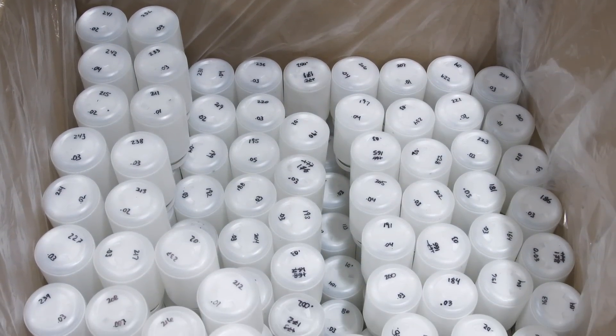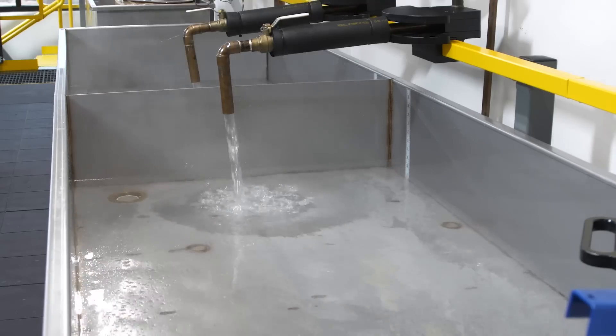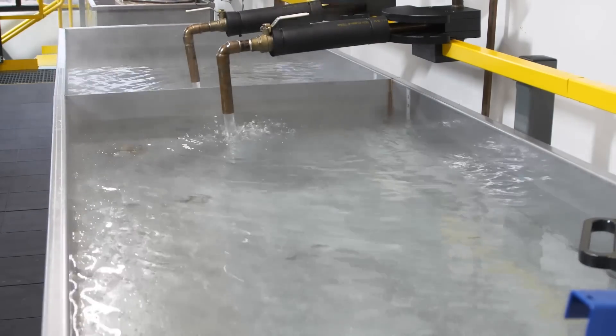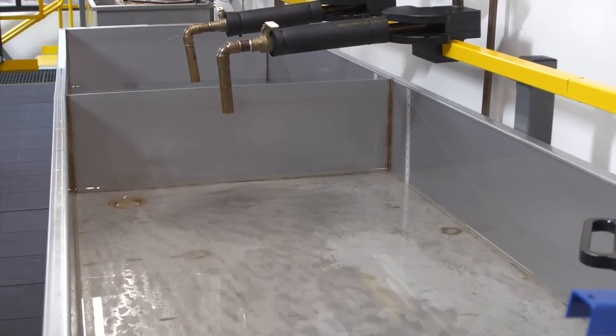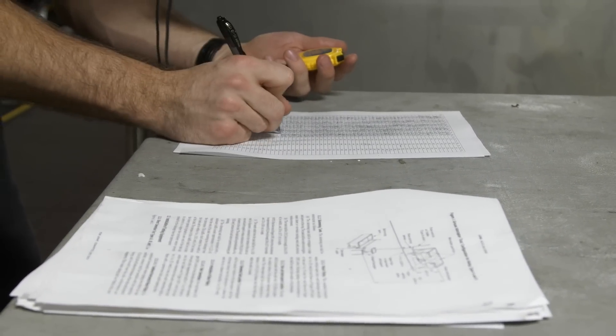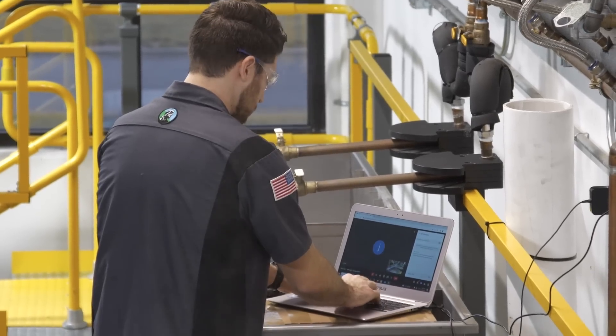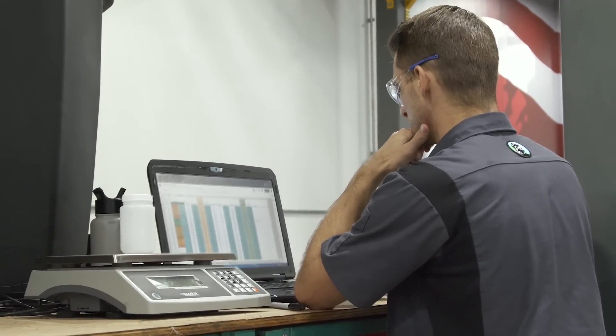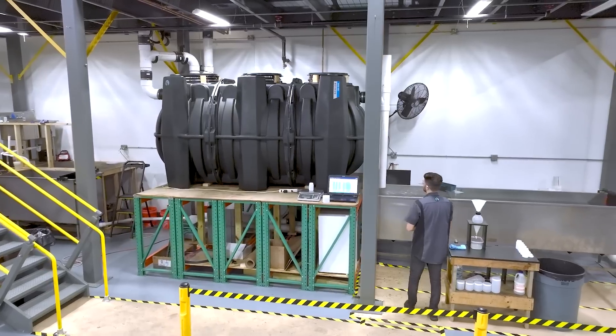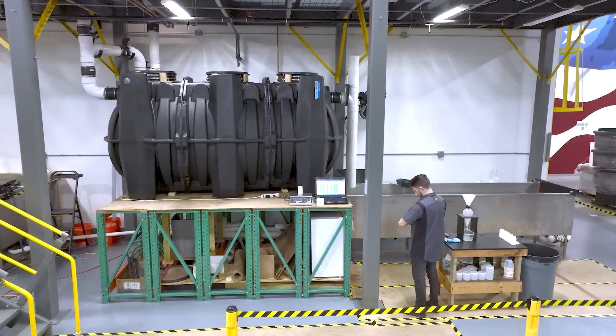We repeat this test over and over until the unit reaches a capacity where efficiencies start to fail. The test fails when the average efficiency drops below 90%, or two increments drop below 80%, or a single increment drops below 75% efficiency. At the end, we have a full test report that outlines all increments from every single run, giving us the maximum capacity of the grease interceptor at a known flow rate and the average efficiency up until that point.